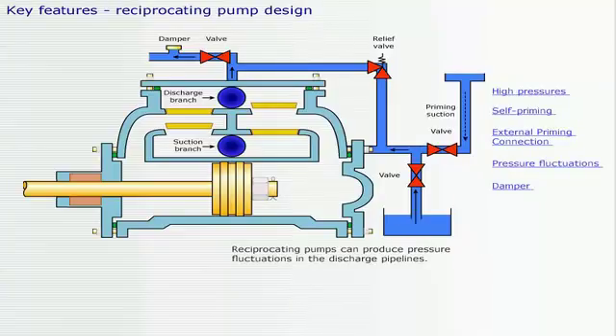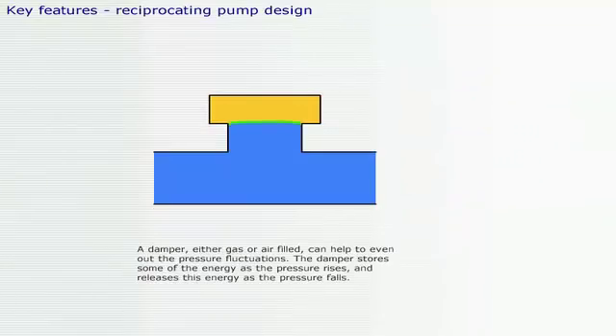Reciprocating pumps can produce pressure fluctuations in the discharge pipelines. A damper, either gas or air filled, can help to even out the pressure fluctuations. The damper stores some of the energy as the pressure rises and releases this energy as the pressure falls.